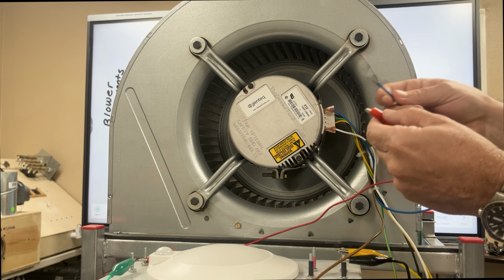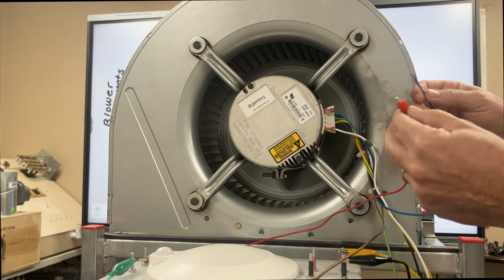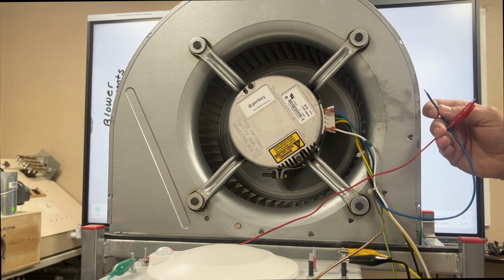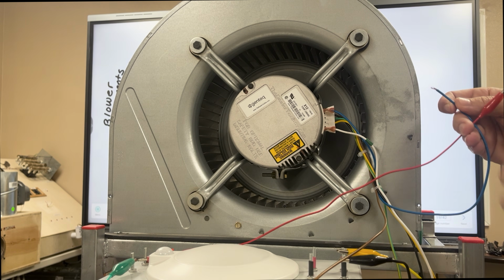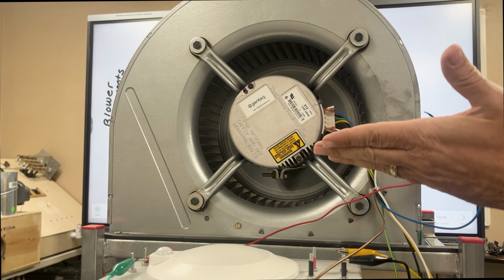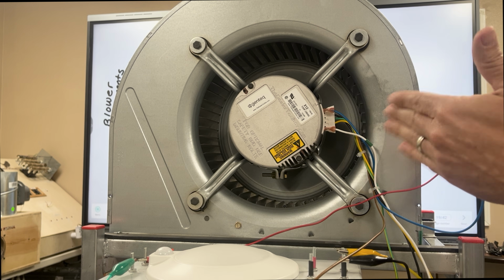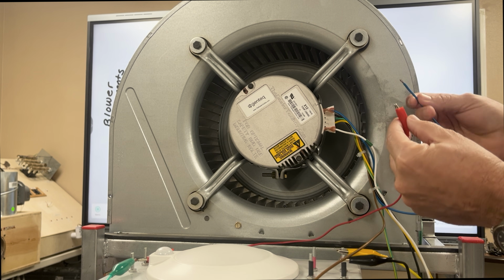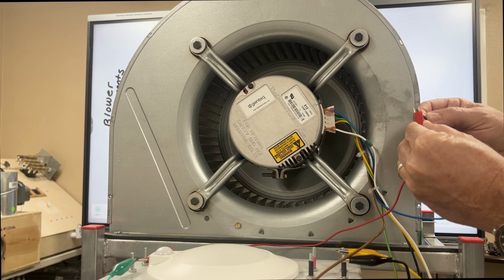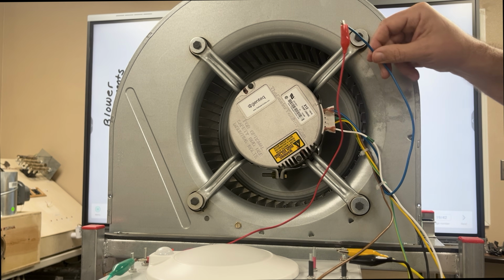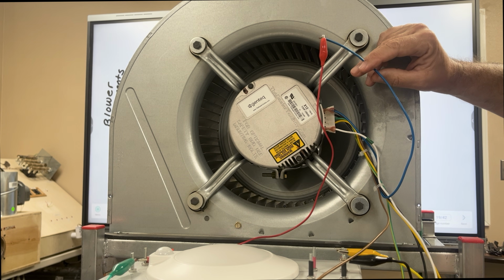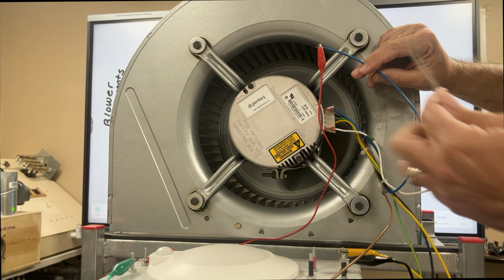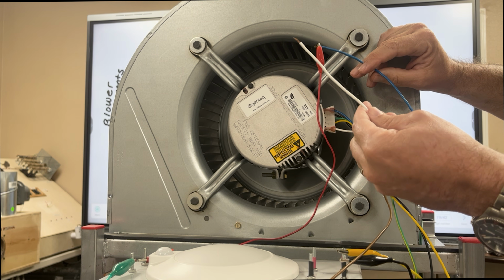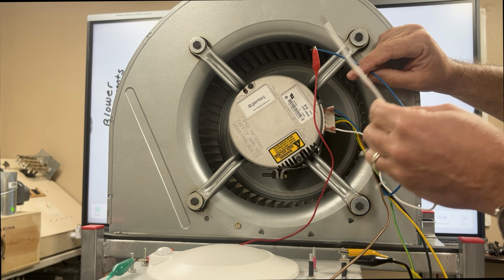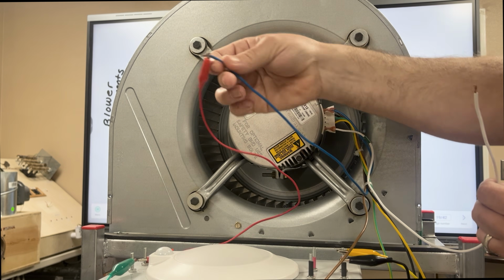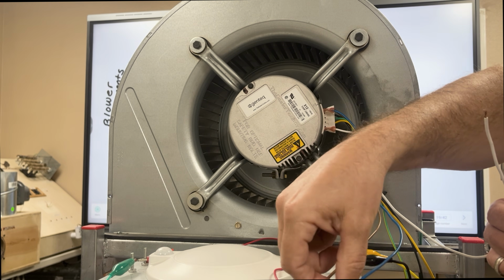So if I wire this to 1, this is low speed. And if I wired it to 5, that would be high speed. Everything in between is a version of medium. So medium low, medium, or medium high. So I'm going to connect to our low speed terminal 1. I'm going to hold up the white wire because this is terminal 5. Okay, and I'm just going to keep this up. I'm going to let this rest safely over here.